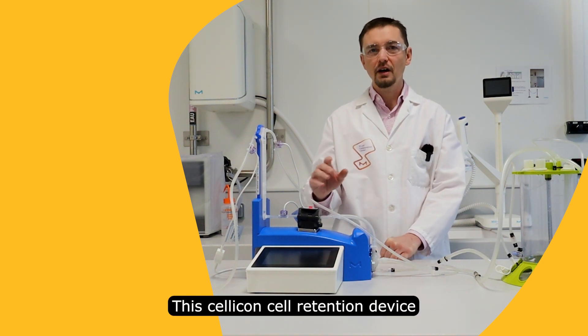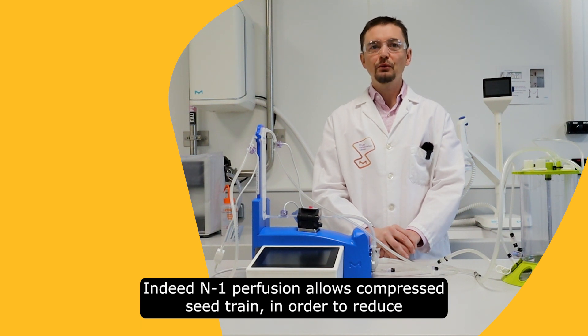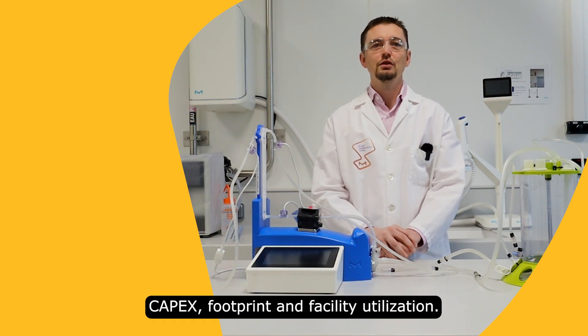The Cellicon cell retention device has been designed for N-1 perfusion to intensify the seed train process. Indeed, the N-1 perfusion allows a compressed seed train in order to reduce capex, footprint and facility utilization.